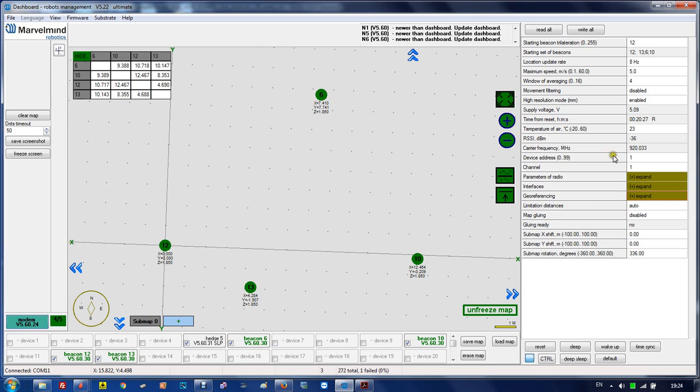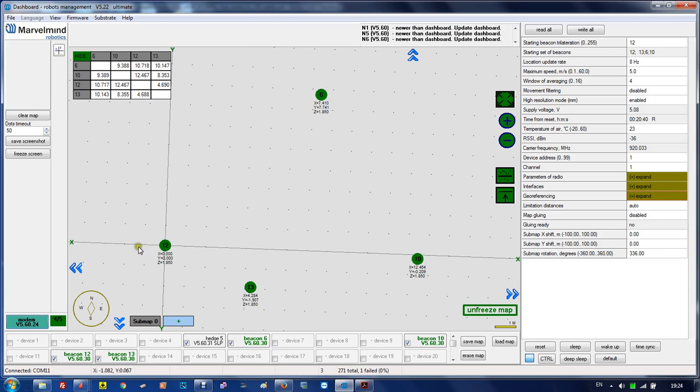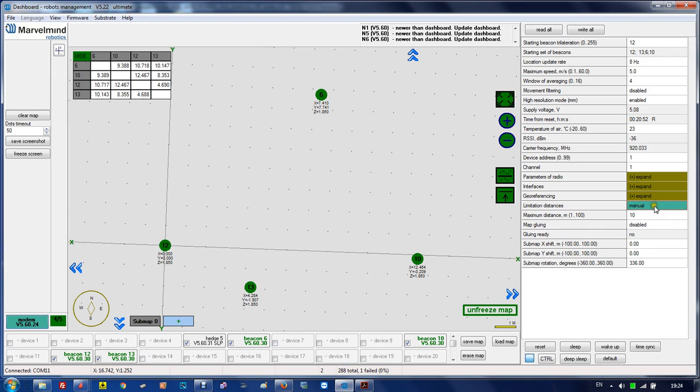Limitation distance is very important. Now the system calculates where to measure ultrasonic automatically based on formulas depending on these distances. It gives you the most optimal update rate in most cases. If you choose it manually, then you must select the right one. For example, 10 for this would be wrong because you have distances up to 12 meters, so it means it will not listen.